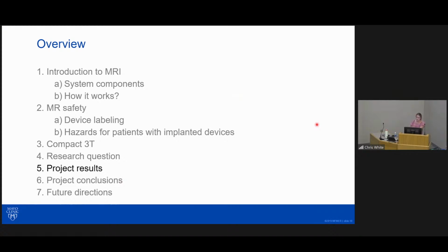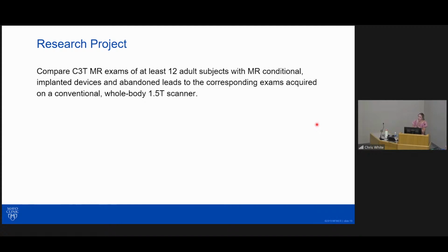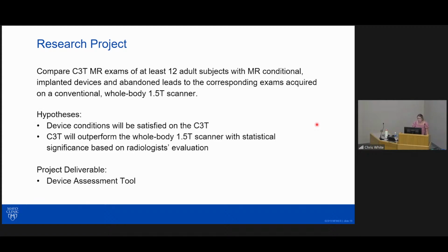So this brings us to our research project. So we want to compare compact 3T MR exams of at least 12 adult patients with MR conditional implanted devices and abandoned leads to the corresponding exams acquired on a conventional whole body 1.5T scanner. The purpose is to establish that the compact 3T scanner operates at least equivalently to a whole body MR scanner for routine brain imaging for patients with implanted devices. So the hypotheses surrounding this project are: first, device conditions will be satisfied on the compact 3T. And second, the compact 3T will outperform the whole body 1.5T scanner with significant results based on a radiologist evaluation. And then the project deliverable is a device assessment tool, which is what I'm going to talk about next.